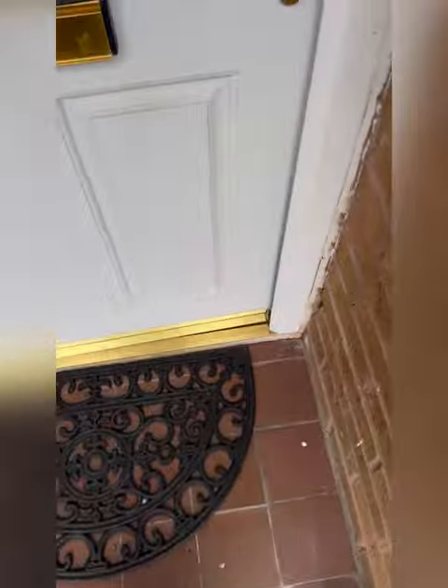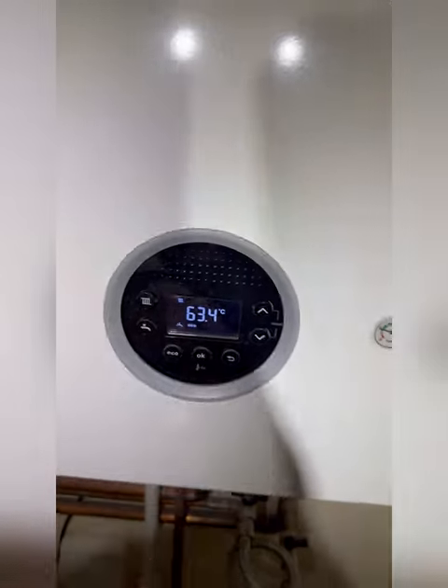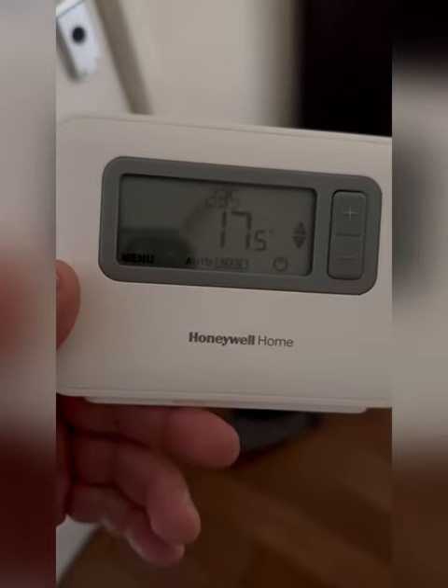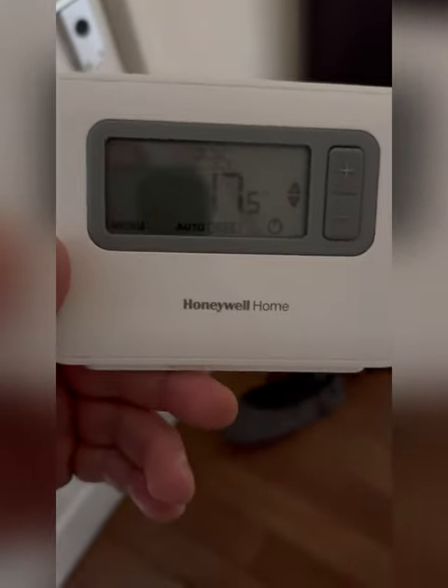Turned up to this one — Worcester Bosch 2000. No heating was the fault; they said they had hot water. Boiler's not doing anything. The programmer's calling, but the boiler's still not doing anything.